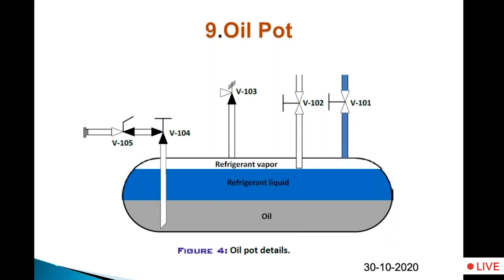because if you open the oil drain valve suddenly, the ammonia and oil will come out, and if the operator by accident opens the valve much more, then he runs away, and the valve remains open, and then there are ammonia accidents. So instead of that, use an oil pot.